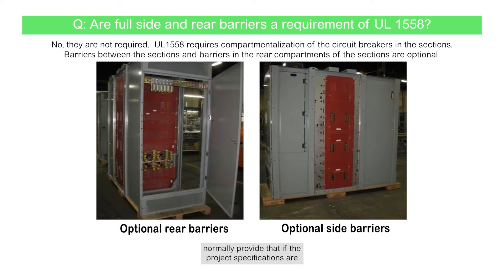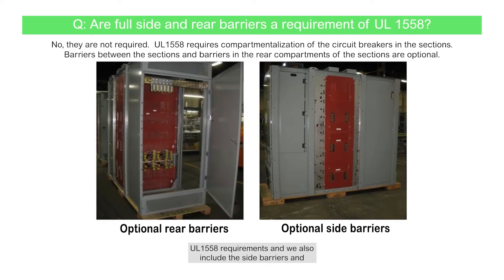We normally provide that if the project specifications are calling for it. We design and build the switchgear to meet UL1558 requirements and we also include the side barriers and rear barriers between sections if the situation calls for it.